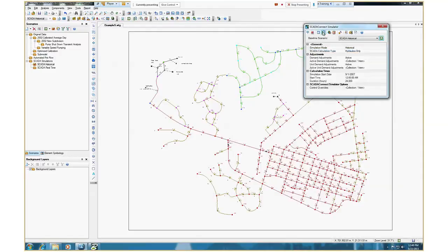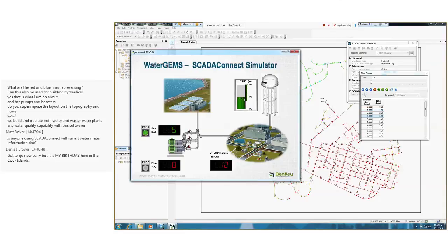and again play it through, and again something similar happens. The tank drains. You see that pump 1 is on, and then the tank drains a little bit more and a little bit more. This time pump 2 does not come on, and now we've emptied out our tank. So you can see that on our SCADA, we're clearly seeing that we've got a pretty serious problem.